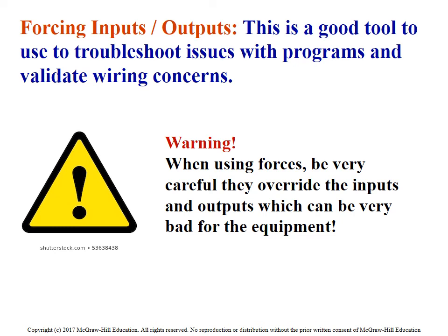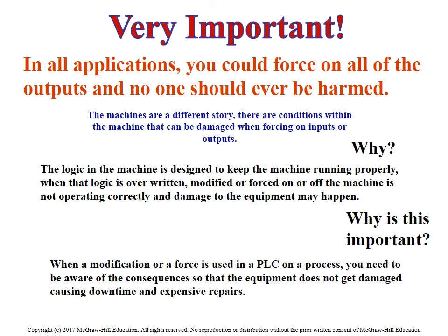And then someday when that input does turn on or turn off when it's supposed to, indicating some kind of fault or maybe some kind of at-position kind of thing, your PLC does not see that, and at that very moment you end up with a machine crash or something gets damaged. One of the very important points, like I mentioned before, is that if you leave a force on, it could do a lot of machine damage.